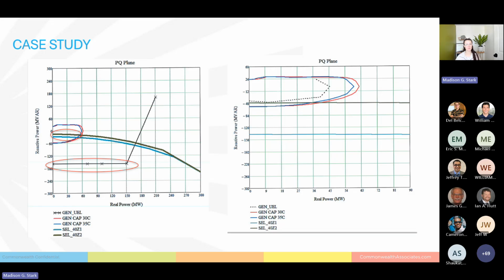Now over on this right side, we see that corrected, where the first thing we hit coming out from unity power factor is this limiter, great. Then we hit our zone 2 relay, perfect. It's going to be slower acting, giving the generator time to respond. We hit our thermal capabilities, okay. And then our zone 1 relay, this is our instantaneous catastrophic event based relay that's going to trip and protect everything that it can.